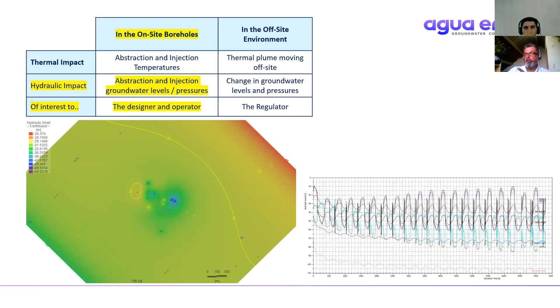Again, I've touched on earlier what the thermal plume might look like. This can stretch off, in this case about 150 meters away from the site. We've got this thermal plume for this cooling-dominant system sending warm water down gradient. That's of interest to the regulator, and also of interest to you as the designer, because we can't adversely impact anyone else.